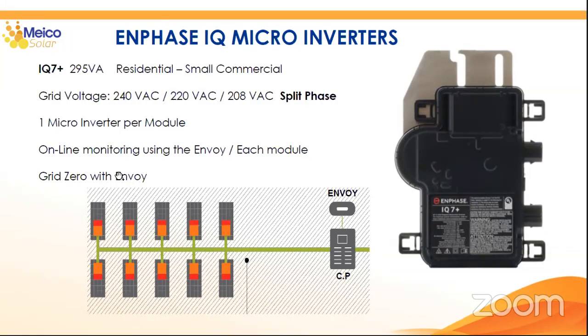And also very important, you have the ability to make the grid zero export with the installation of the Envoy. Okay, so with setting the Envoy and adjusting the Envoy with the settings you need, you can have the zero exportation management of the project. So if you don't want to go and sell energy to the grid, you can do it. If you want to sell, you can do it also. But this is something that is very, very important, because with other microinverters, you're not able to do this. So when you don't want to make any export to the grid, this is something you can do with ENPHASE without having to put any additional pieces or accessories to the project.